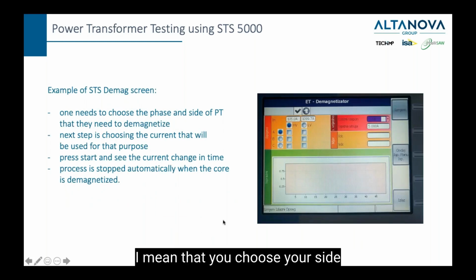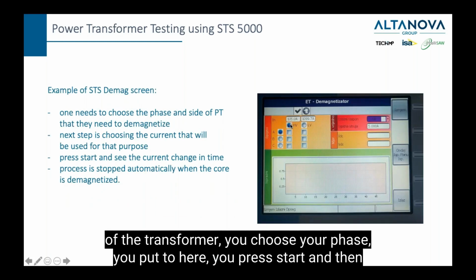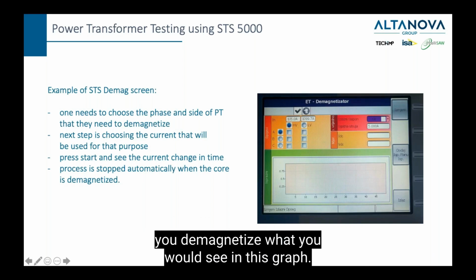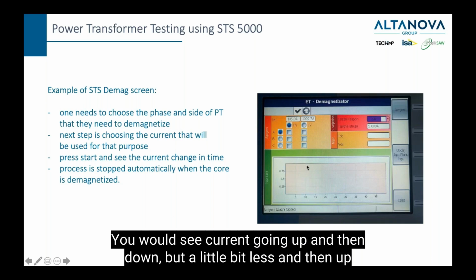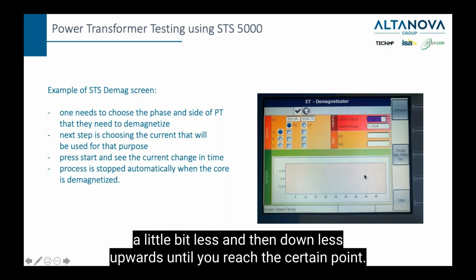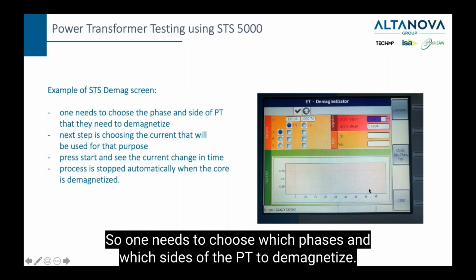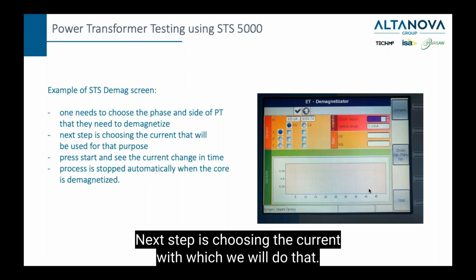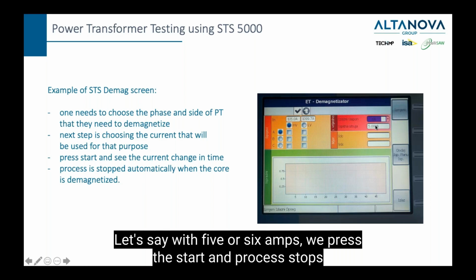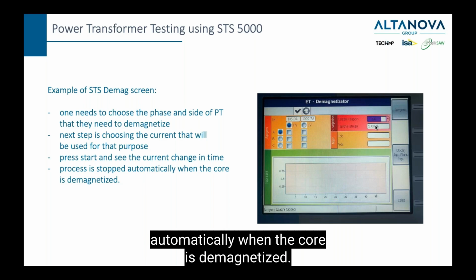What do I mean by that? I mean that you choose your side of the transformer, you choose your phase, you put a tick here, you press start, and then you demagnetize. What you would see in this graph is current going up and then down, but a little bit less, and then up, a little bit less, and then down, less, up, less, until you reach a certain point. So one needs to choose which phases and which sides of the PT to demagnetize. Next step is choosing the current with which we will do that, let's say 5 or 6 amps. We press start, and the process is stopped automatically when the core is demagnetized.